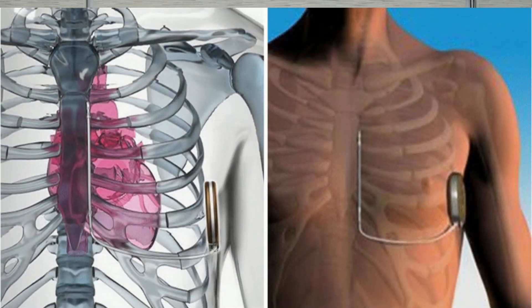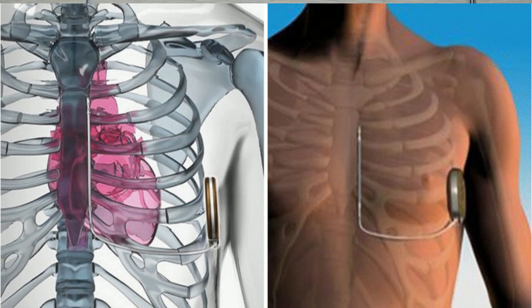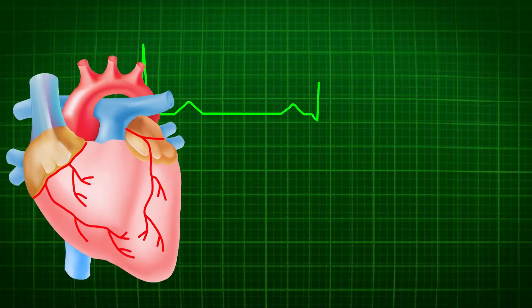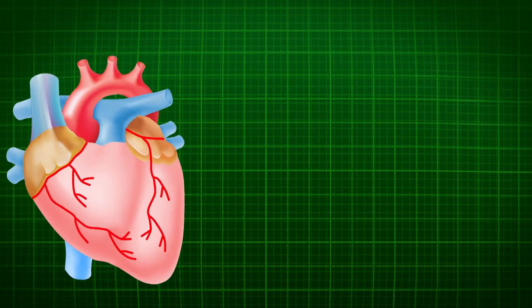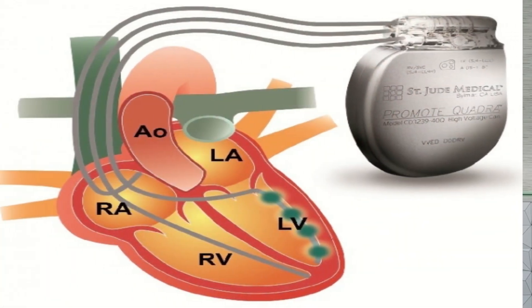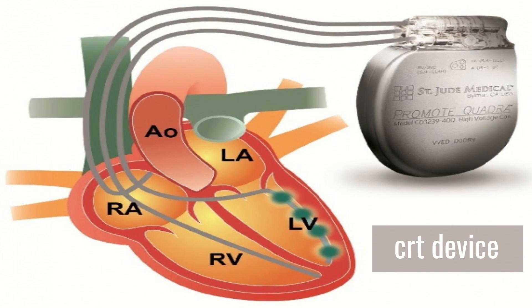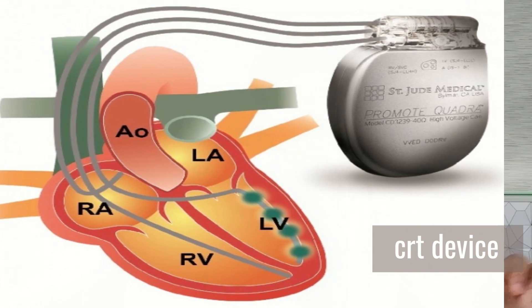This device does not improve the pump function of the patient — it only works when the patient is having a low or high heart rate. It can pace the heart when the rate is low and revert the rhythm when the rate is high. It will only be functional when the patient is having rhythm problems. To improve pump function, there is another device — a triple-chambered pacemaker known as the CRT device — which we will discuss separately. But this AICD device does not improve pump function.